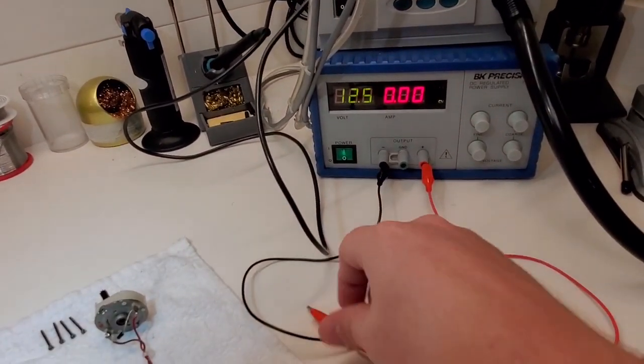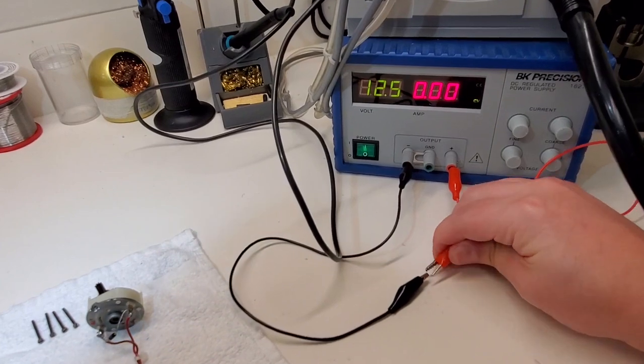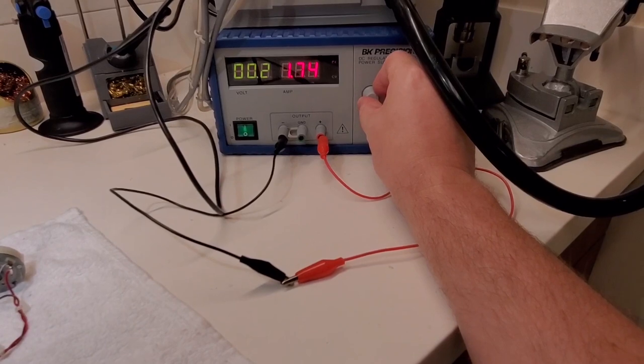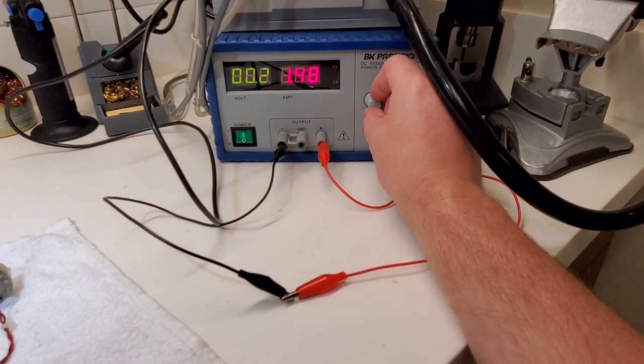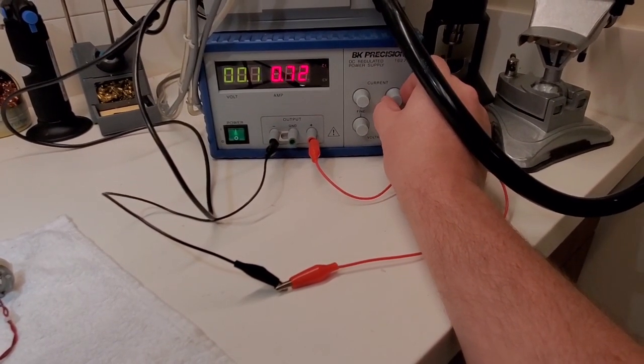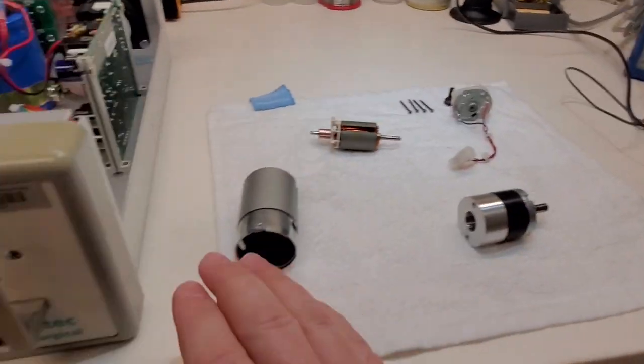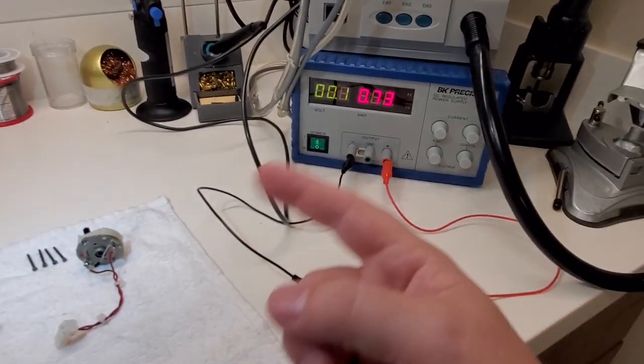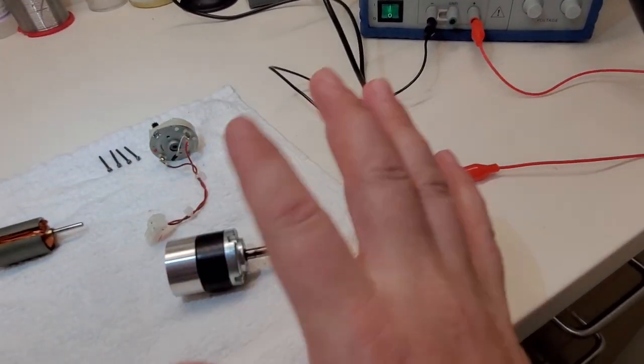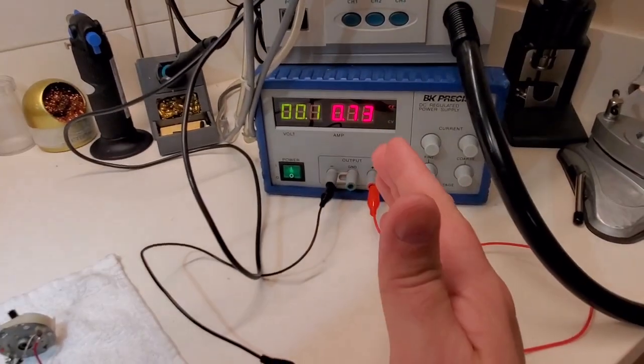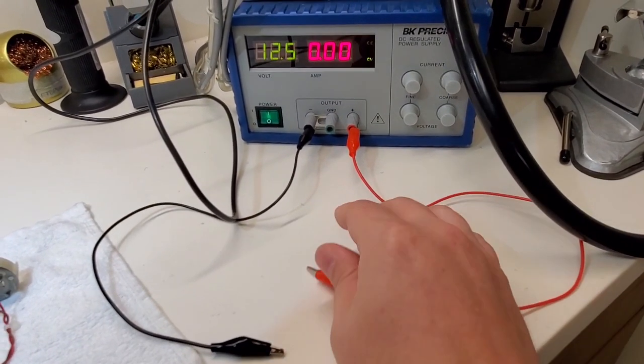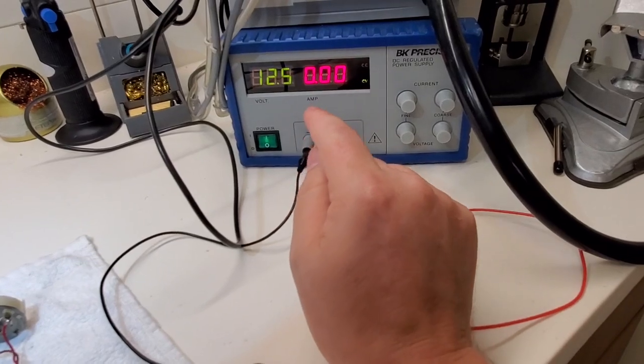So one of the first things that you're going to do when testing out a motor like this is you're going to set your current. So you clip your leads together and you set your current, which I'm going to turn this guy way down. Now if this motor was good, I should be able to run it with less than an amp worth of current because there's no load. I don't have a tubing set on there, so the motor is just free-spinning. The only drag is going to be this planetary gear reduction, but we'll go into that in a moment when we go into the teardown. So what I did is I connected my power supply, I set it to less than an amp, and then when you disconnect your leads, now you set your voltage.